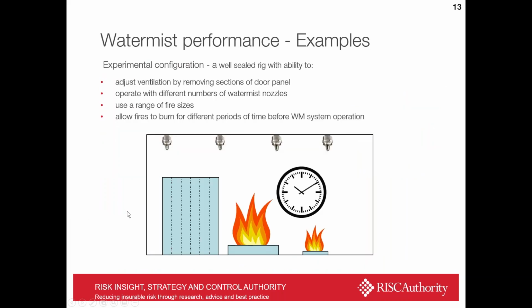So I said that I would give you a good example on some of these facets. Here was a very simple series of tests that we did, but they were very well controlled in a 100 cubic meter enclosure, very well sealed rig, but we can adjust the ventilation by removing sections of the door panel, the blue blob on the left there with those dots, those are the sectioned door panel. We can operate with different numbers of Watermist nozzles. We could use a range of fire sizes, and we can allow the fire to burn for different periods of time before the Watermist system operates. And hopefully the results from this will show you clearly how counterintuitive some of the operating modes are.